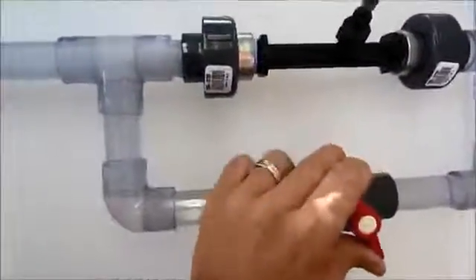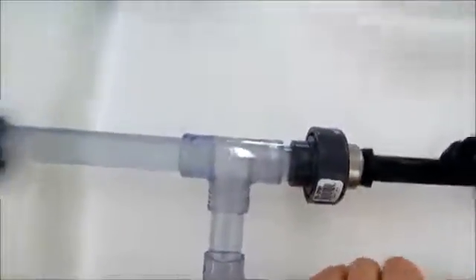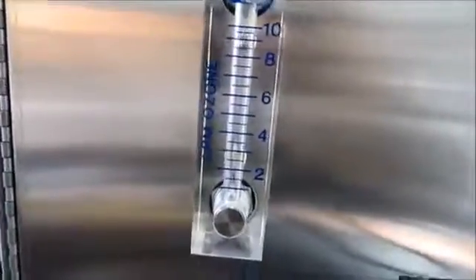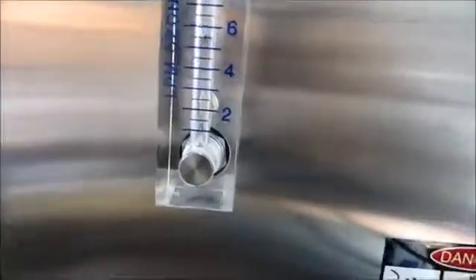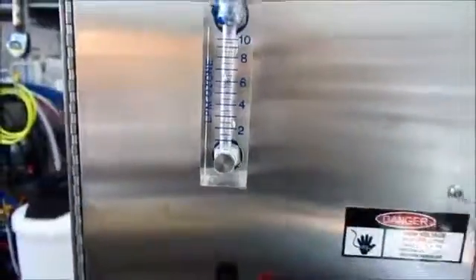And you can see when I open the bypass, you can adjust it for less gas and more water. So now it's open. The ball valve's all the way at the bottom. There's no pull. But when I start to close down the ball valve, the gauge reads more and more suction. So we want it set to about midway again on the gauge.